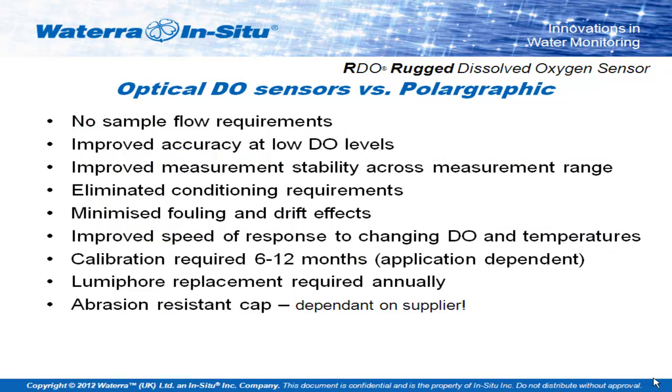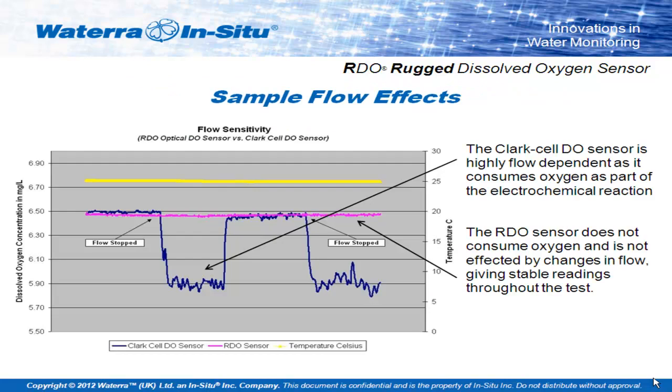Key advantages for optical dissolved oxygen over traditional galvanic and polarographic sensors: you don't need a flow, so you don't need to stir the sample. The polymer foils on the front of the sensor caps are much more abrasion resistant than the membranes on traditional Clark cells, so you can use them in particularly harsh environments — chemicals, bio-remediation in groundwater systems, silt-laden waters in wastewater treatment plants. You also get a very stable reading at low dissolved oxygen. If you've ever used galvanic or polarographic sensors, you'll know they're quite difficult to calibrate at a zero oxygen point.